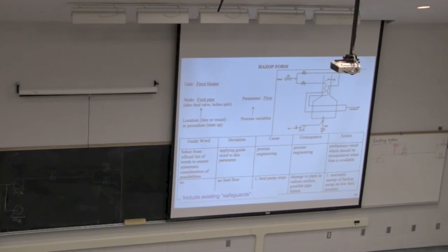Okay, so you see how this gets messy, right? There are many alternatives we have to consider. So yeah, we could have a valve, but then we want to instrument that valve so that it's always open. Okay, and that it will alarm if it's shut.